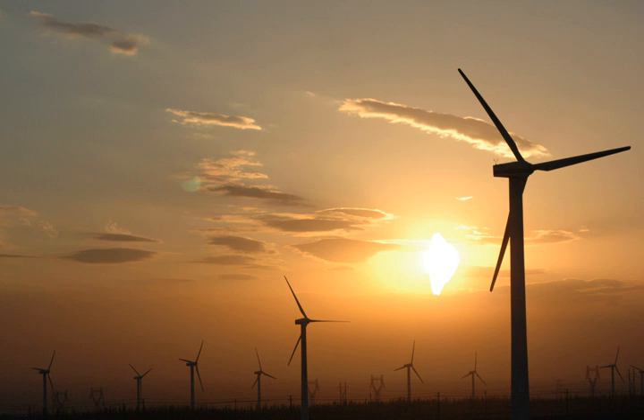Three reports on the wind variability in the UK issued in 2009 generally agree that variability of wind needs to be taken into account by adding 20% to the operating reserve, but it does not make the grid unmanageable. The additional costs, which are modest, can be quantified. The combination of diversifying variable renewables by type and location, forecasting their variation, and integrating them with dispatchable renewables, flexible fuel generators, and demand response can create a power system that has the potential to meet power supply needs reliably. Integrating ever higher levels of renewables is being successfully demonstrated in the real world.